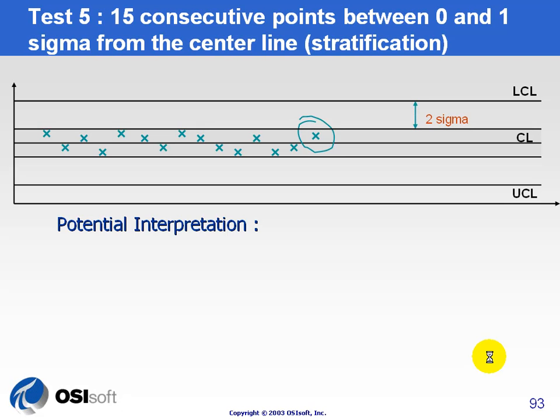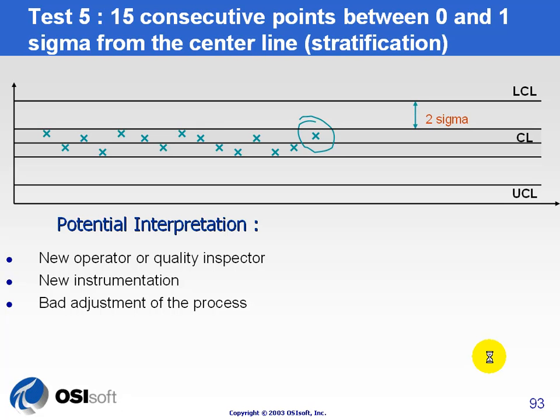Test five is the fifteen consecutive points between zero and one sigma. The potential interpretation is you've got some kind of operator or inspection error, the instrumentation is new, or there's a bad adjustment of the process — things are not getting the normal variability you would expect. If data is coming from different manufacturing sources, in other words if the source of the data is not the data that was used when you were developing the SQC alarm limits, then the limits you have must be too broad, or else you wouldn't get so many within one standard deviation.